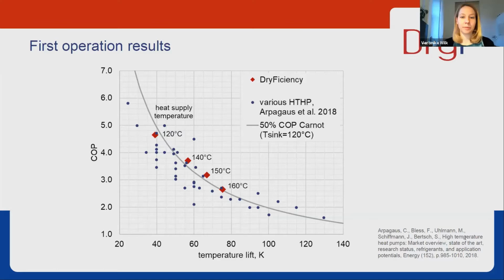We compare them to the DryFiciency heat pump based on the temperature lift, because this is a sound comparison. The gray line indicates the relationship of COP and temperature lift for an ideal heat pump reaching 50% of second law efficiency for a heat sink temperature of 120. So this is just a rough indication to show the behavior of the closed loop heat pump.